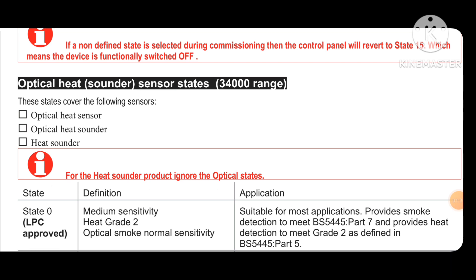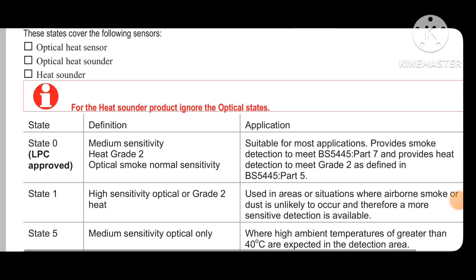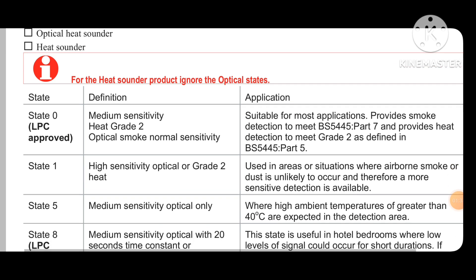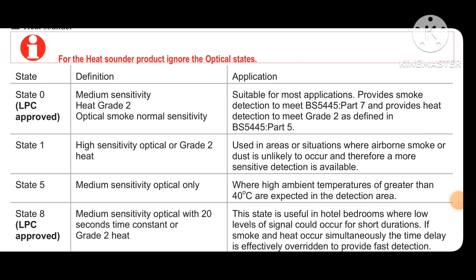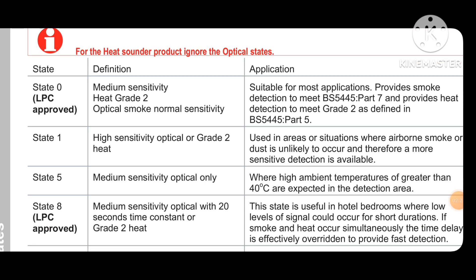For the optical heat sounder sensor, state 0 is medium sensitivity. We have to consider sensitivity according to locations — whether the area has clear air, or is dirty or dusty. If we put state 1, that means high sensitivity, but we should only use high sensitivity in clear air areas. If the air is very dirty or there are chances of more dust, we put medium sensitivity.